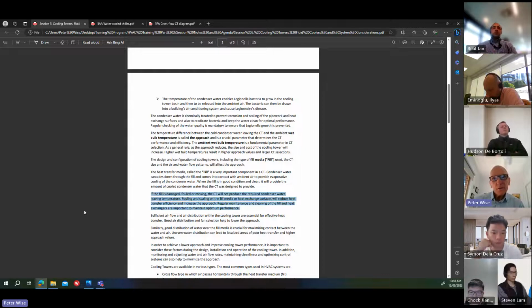But because the air picks up dirt and so on and passes through the fill, it will get dirty over time. It may get damaged when it's being maintained, or parts of it might even be missing. I've seen all these things happen. People take some fill out to clean it or repair it, and it doesn't go back in. So if the fill is damaged, fouled, or missing, the cooling tower will not produce the required condenser water leaving temperature that you've designed it for. Fouling and scaling on the fill media or heat exchange surfaces will reduce heat transfer efficiency and increase the approach. So increasing the approach means the cooling tower is not performing the way you want it to. Regular maintenance and cleaning of the fill and heat exchangers are important to maintain optimal performance. So I've got a couple of pictures of fill so you know what it looks like.